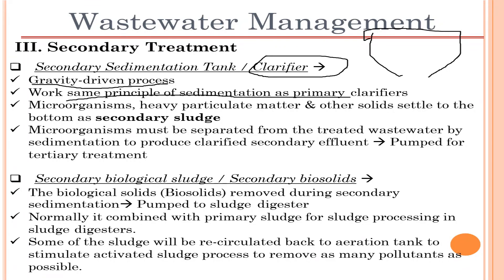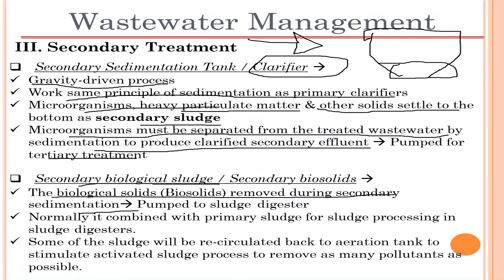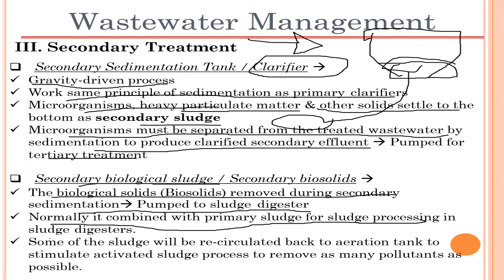In the secondary clarifier, microorganisms and heavy particulate matter settle to the bottom as secondary sludge. Microorganisms must be separated from the treated wastewater by sedimentation to produce clarified secondary effluent for tertiary treatment. The secondary biological sludge — biosolids — removed during secondary sedimentation is pumped to the sludge digester, where it combines with primary sludge. Some of this sludge is recirculated back to the aeration tank to stimulate the activated sludge process and remove as many pollutants and suspended solids as possible.